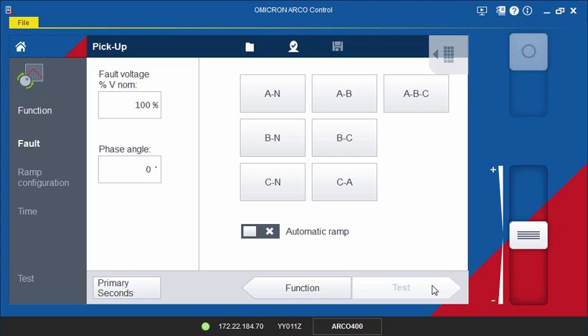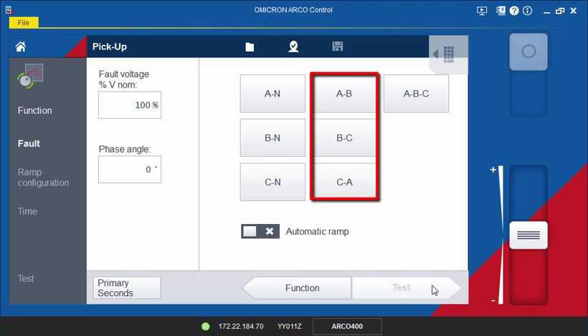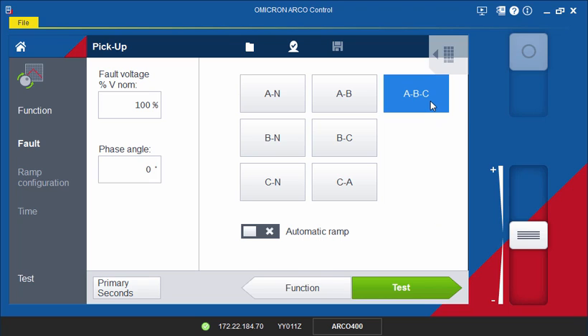First, select the phase which should be tested. Depending on the fault type, either one, two, or all three current output values will be ramped. In this example, choose the three-phase fault to test the pickup value of the phase elements.